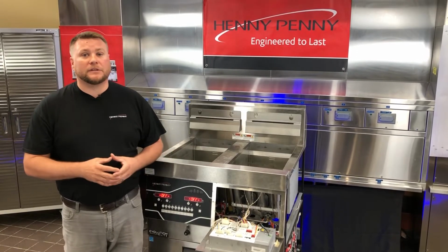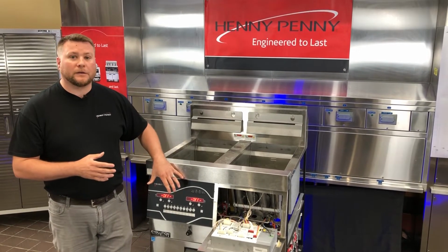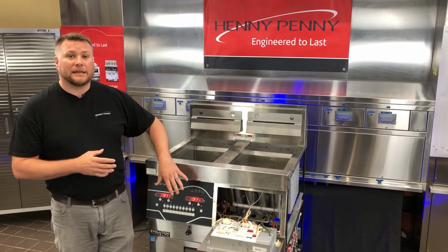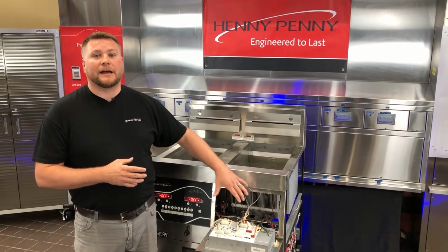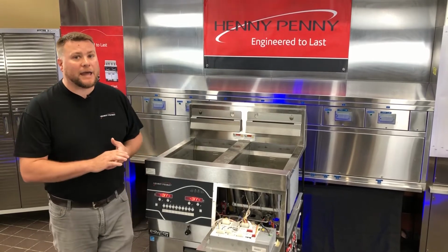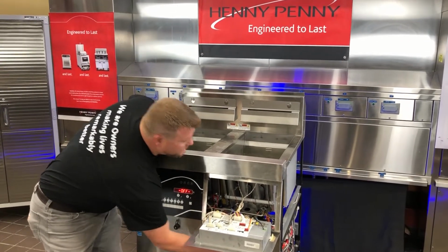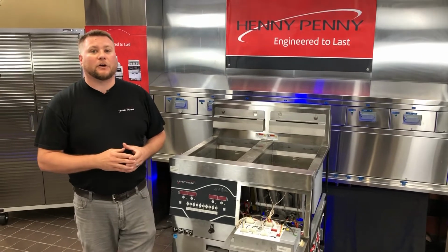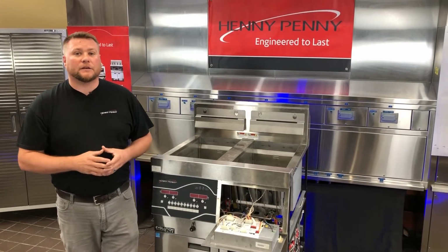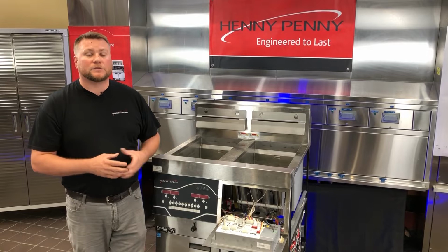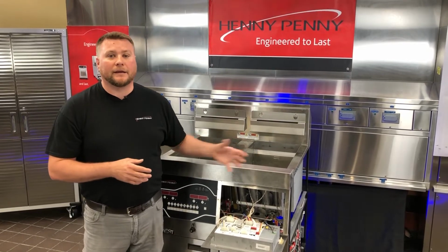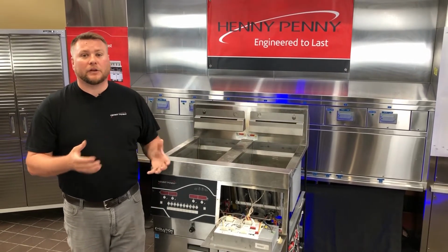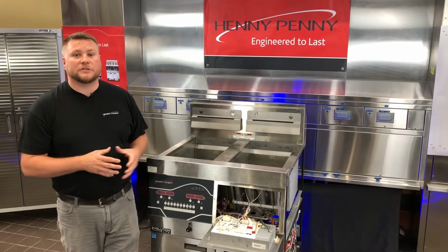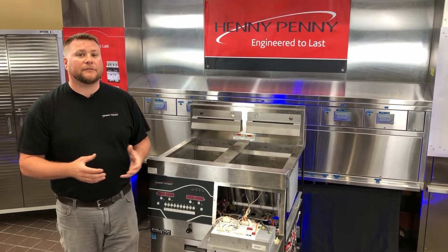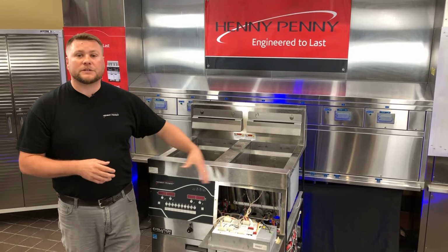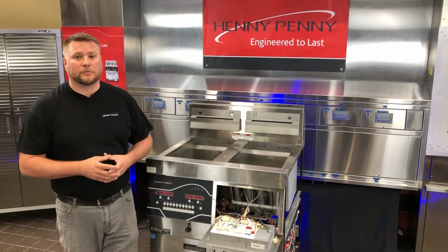When troubleshooting that E-60 error code on one control panel only, we want to start by swapping our control with the VAT right next to it. But before we do that, we want to make sure we turn our main power switch off so we don't run the chance of damaging any sensitive electronics on the control board or AIF board when unplugging and plugging in those connectors. We always want the unit powered completely down before swapping those components.